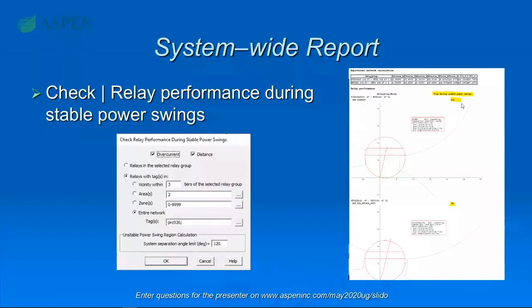Currently we support five different event file types: EVE and CEV from SEL, CFG is the COMTRADE format, PQD is in PQDIF format, and TXT is the Aspen-defined format. We select a sample CEV as the input file. The dialog box for a single event file shows the directory to the event file, drawings of three-phase voltage and three-phase current. We can display waveform phase of magnitude and apparent impedance — most of the time we use phase of magnitude, which is extracted from the waveform with Fourier transform.